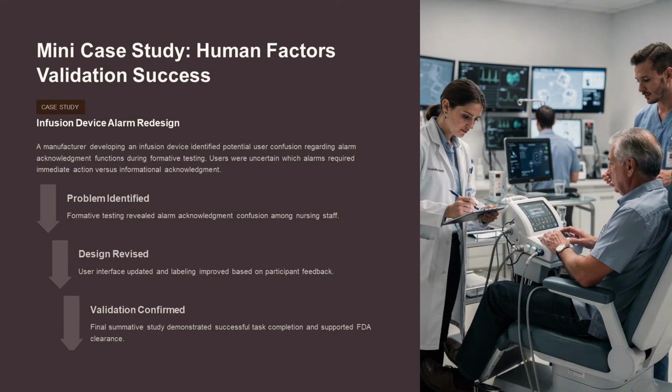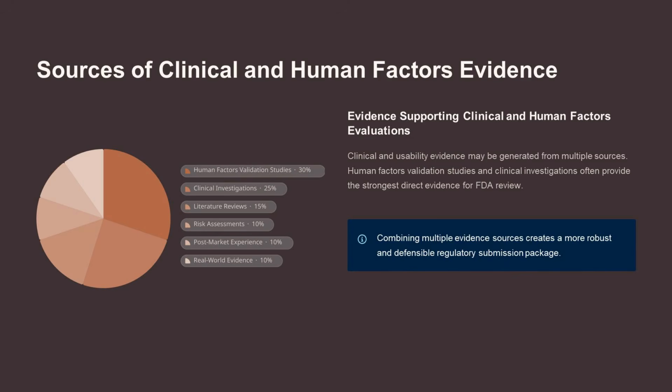A case study on infusion device alarm redesign shows how formative testing identified problems, leading to design revisions and successful validation. Combining multiple evidence sources creates a robust regulatory submission package. Human factors and clinical investigations often provide the strongest evidence for FDA review.